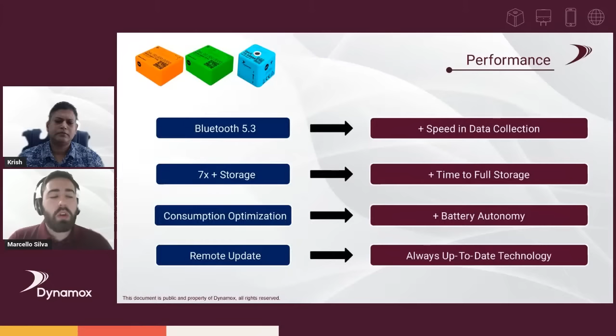Okay. In terms of new monitoring modes, just to give an idea, these new sensors will have these configurations available. So what are telemetry profiles? Basically, you can define up to two different profiles to be monitored in terms of continuous or telemetry data. Imagine you have an asset that usually has some very distinct failures, in the low frequency range or the high frequency range. You can define metrics, different levels, and different profiles for each of those monitoring modes. Imagine I want to define a profile for the high frequency range, so from 50 to 13K, for example. I would preferably use the acceleration metric to monitor that.